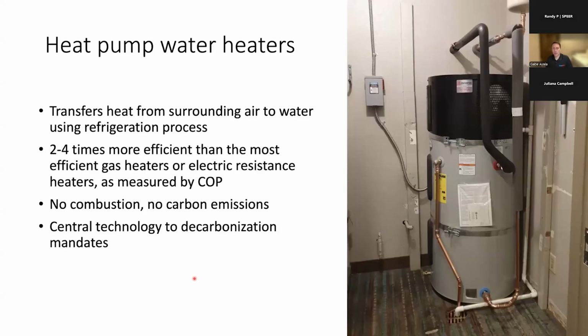But they are different. There's no combustion, right? It uses basically a compressor to extract the heat from the surrounding air, using the refrigeration process, and put it into the water. And it makes hot water very efficiently. When it works great, they work very efficiently, like 2 to 4 times more efficient than even the highest efficiency condensing gas water heater. There's no carbon emission, there's no combustion. You don't have to worry about carbon monoxide poisoning. So there are a lot of great benefits to a heat pump water heater.